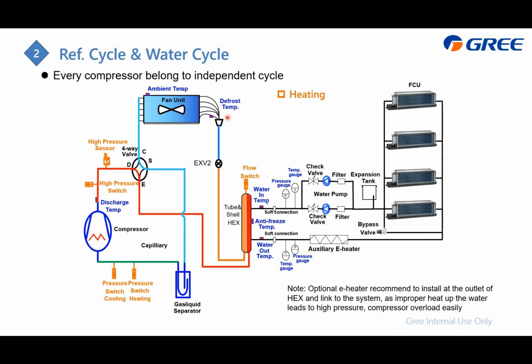Also focus on this refrigerant cycle. This is for the on-off, how we control it. And for the inverter, if you remember well, on the last slide we had the IPM module here, right? Which is this one. This time, the refrigerant will get expanded at this EXV2. This is for heating. EXV1 is for cooling. The purpose of setting two EXVs here is just to ensure the refrigerant that gets through this IPM module will not be that cold. If it is very cold, it will make condensing water, and the condensing water will absolutely damage this IPM module, which we need to avoid. So, this is all for the refrigerant cycle.